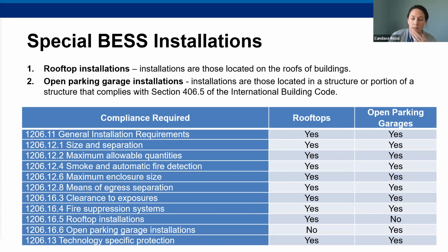Once again, they will have to meet all the general installation requirements that we've gone over, alongside the size and separation, maximum allowable quantities, and smoke and fire detection. And as you go down, there are some additional requirements in 1206.16. So, almost the bottom 4, and then they're still required to meet all the technology specific protections. Basically, no matter where these systems are installed, they must meet the technology specific protections that we went over, which were the thermal runaway, the explosion control, and the spill neutralization. And then there are specific ones for, obviously, the rooftop systems, which do not need to meet the open parking garage installation requirements, and vice versa.